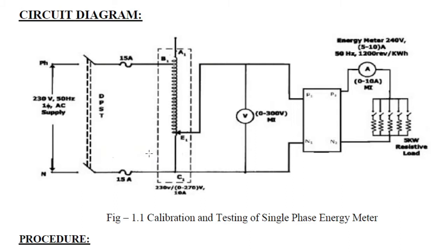There is a disc in the induction-type energy meter which rotates based on the amount of load — if the load is more, the disc rotates faster. As we increase the load, the speed of the induction disc increases. We will find the time taken for 10 revolutions for each load, from which we can calculate the meter constant — number of revolutions per kilowatt hour — and compare with theoretical data to find the percentage error.